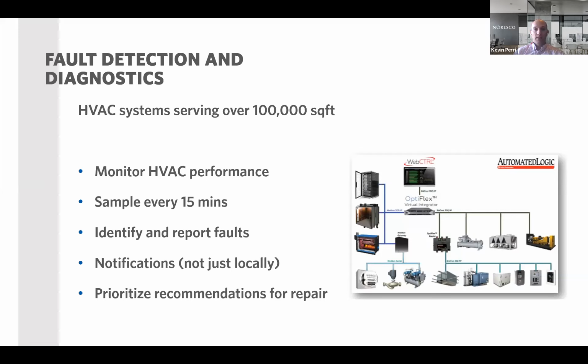So what does this mean? This means that maybe the code is starting to push towards analytical systems. There are several out there that have been around for a few years now. These building analytics are becoming more and more popular because they basically do the hard work for you. You don't actually need a human to tell you that a potential sequence or system is running wild. Why not have a computer tell us that, so we don't have to dig deep through that. So this is a big change. All HVAC systems serving over 100,000 square feet need to have some type of building analytics, for lack of a better term, but if you want to follow a definition, fault detection and diagnostics.